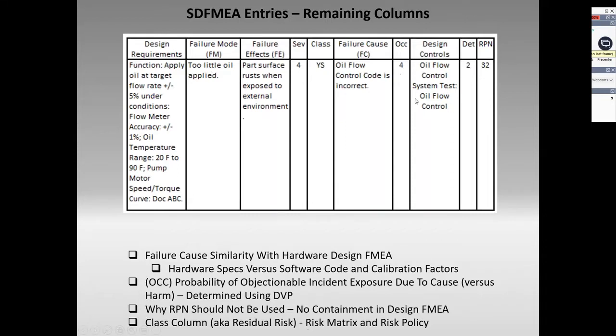So if any of you have ever been in a design FMEA before, and while you're in the room you determine the occurrence ratings—Dave said a bunch of you have FMEA experience—I ask, how did you do that? Because until you do this design verification, you can't assess the adequacy of this code in preventing this too little oil. This detection rating is the effectiveness of this method in assessing the adequacy of this code in delivering the amount of oil we want to deliver.